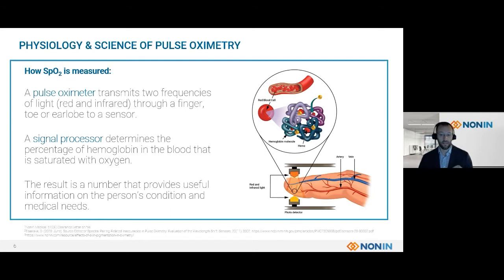Really importantly, these sources of light are essentially our source of truth. So impure light sources can shift the calibration and affect the accuracy of these measurements. And this is most notably at levels that are really important for the health of the patient, at saturations below 95 and darker skin pigmentations that are in some people. Therefore, when Nonin puts together probes and pulse oximeters, it's very important to have the highest quality LEDs. That makes the difference in your measurements.